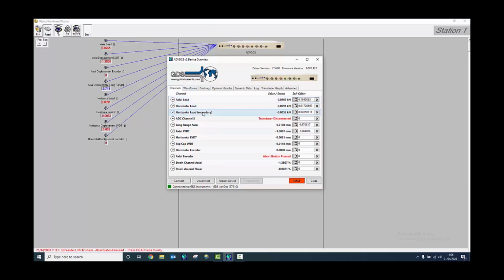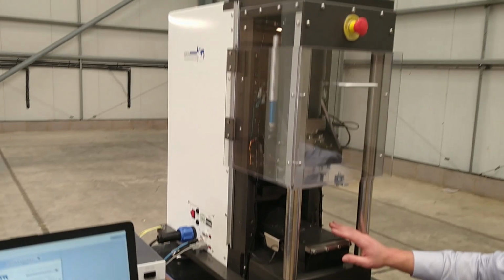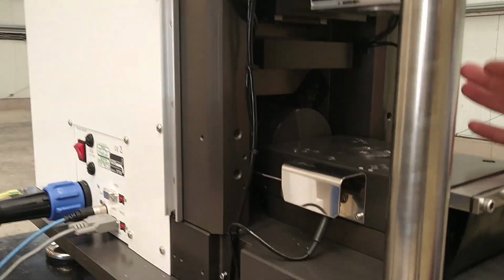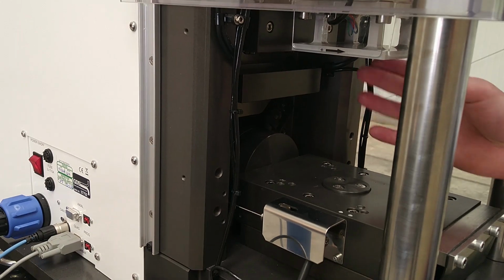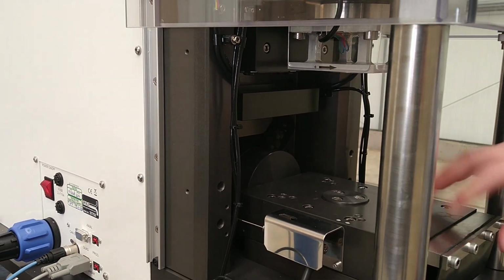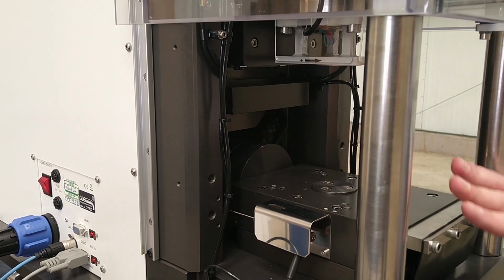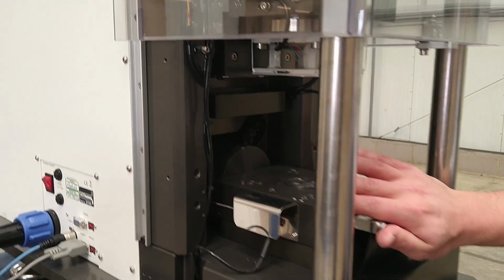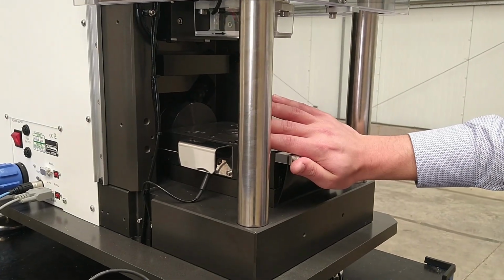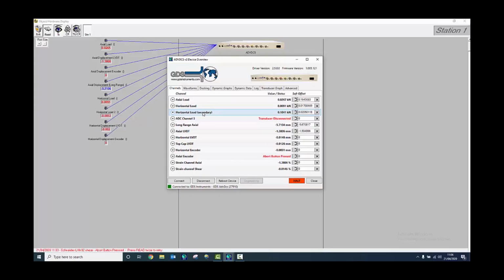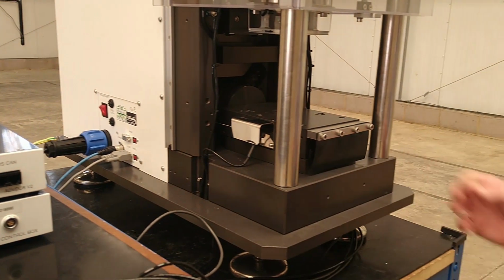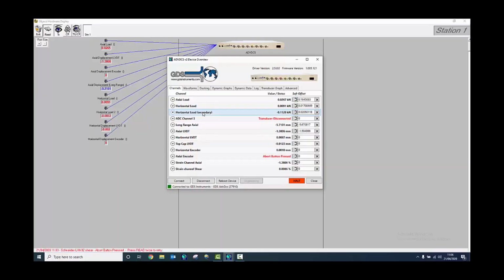And so the last of the load cells will be the horizontal load cell, which sits on the back of the machine, as explained earlier. So if you think about the setup, for this load cell to read positive, that load cell will read negative because they are the opposing forces, which means if I push on the load cell, on the carriage, it should start reading positive values. And if I gently pull on the carriage, the values should change to be negative. So those would be the checks on our load cells.